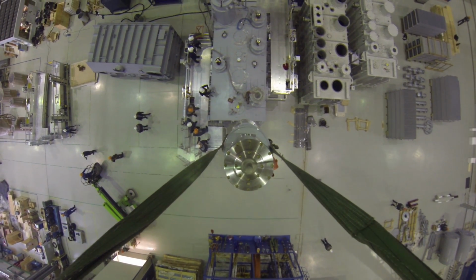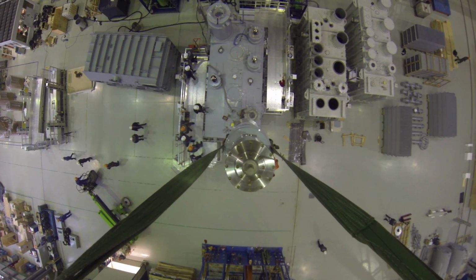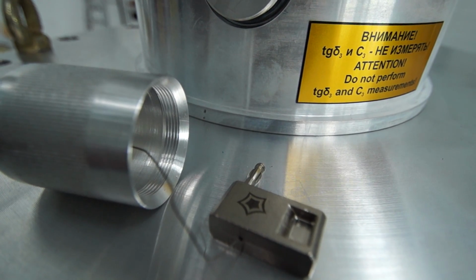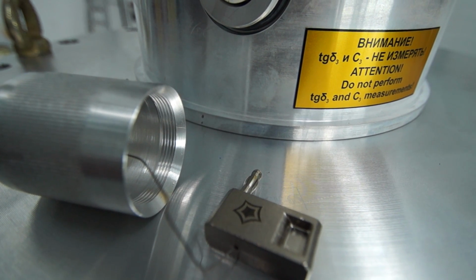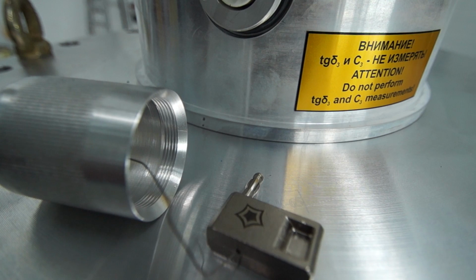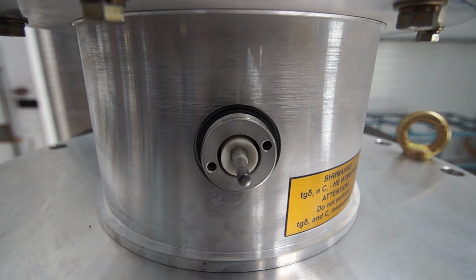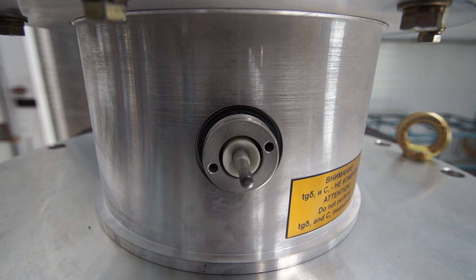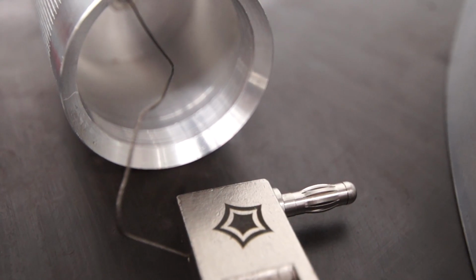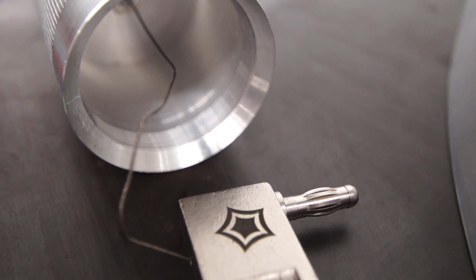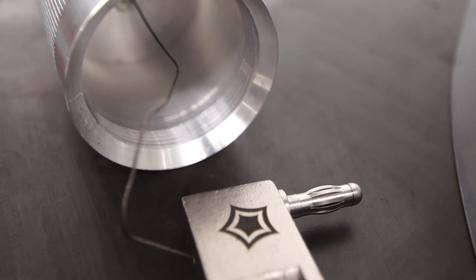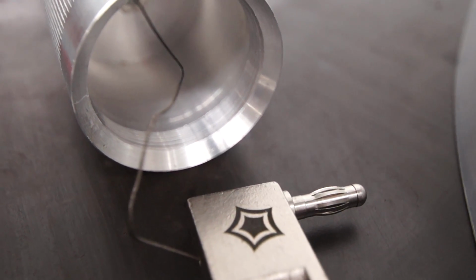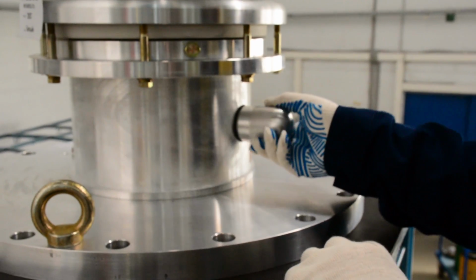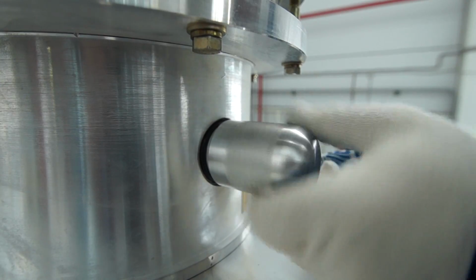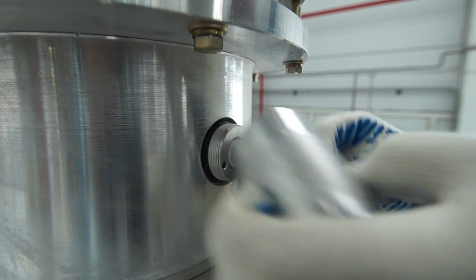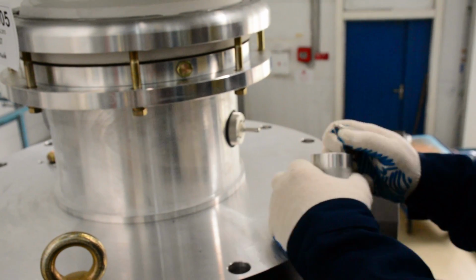Let us now turn to an important process of the proper test tap grounding. The grounding is done with the help of a special-purpose multi-contact attached to the hood of the test tap with a wire. The function of the hood is sealing of the test tap cavity and protection from mechanical damage, whereas the wire will not allow losing the grounding multi-contact. In order to unground the test tap, it is required to unscrew the hood and take off the multi-contact from the pin of the test tap. It will ensure the test tap ungrounding and possibility of internal insulation condition measurements. After the measurements are performed, the bushing must be grounded.